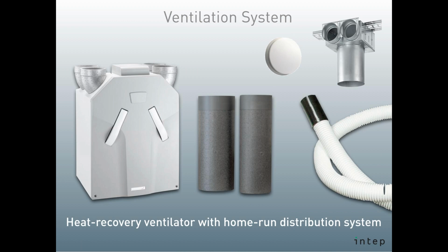The pipes that you see on the right-hand side are flexible pipes made from plastic, and they're essentially like PEX tubing for your plumbing, but in this case, you blow air through them, and they connect from a central manifold to these outlets you see on the upper right-hand corner. And then the little white thing you see next to it is the grate, or the diffuser, I'm sorry, that would plug into the bottom of the ceiling outlet and squeeze the air into a space or suck it back out. So in a nutshell, that's what that is.